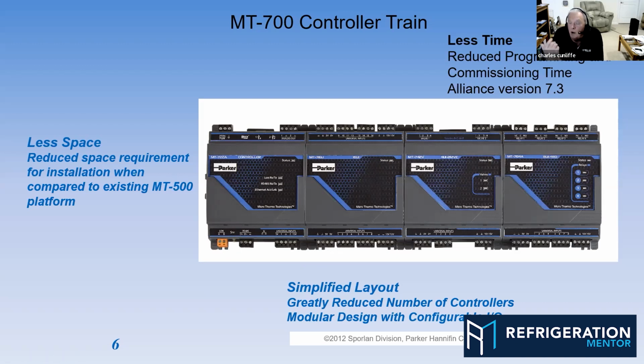That's how we integrate. We don't have to do any jumper wires, or any dip switches, but you push the service pin, you release it, and then automatically the integration is done for you. But now I don't have to do that 10 or 12 times over. I have to do it once. And then it integrates, programs, or flashes the program and all of the set points onto that train. Which makes startup and commissioning so much easier instead of having to commission 40 different boards down the train all over the damn place. Oh my goodness.